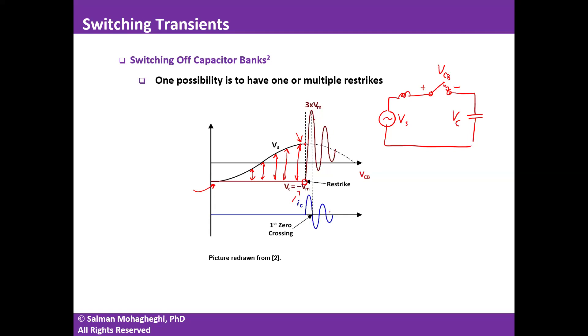The system voltage returns to its sinusoidal waveform. Now with the capacitor at 3·V_M, and the system voltage reaching minus V_M, the difference is 4·V_M. If another re-strike happens, the capacitor pulls the system voltage to 3·V_M and oscillates again. If the arc extinguishes at the next zero crossing, the capacitor could be left at minus 5·V_M.